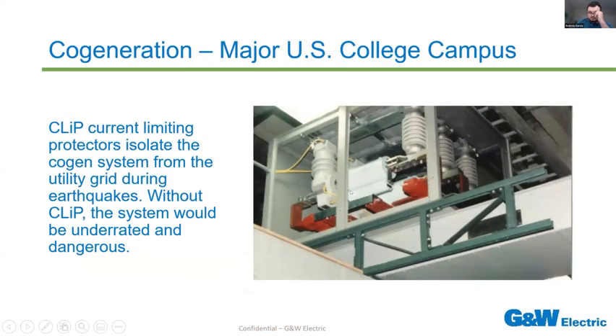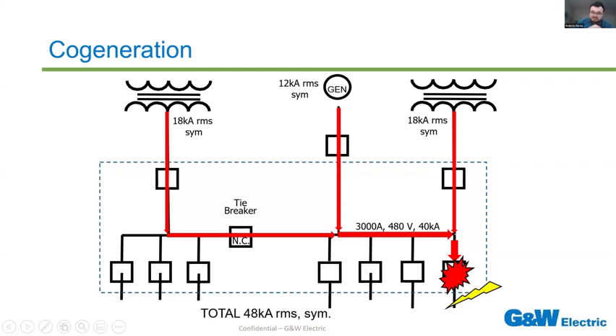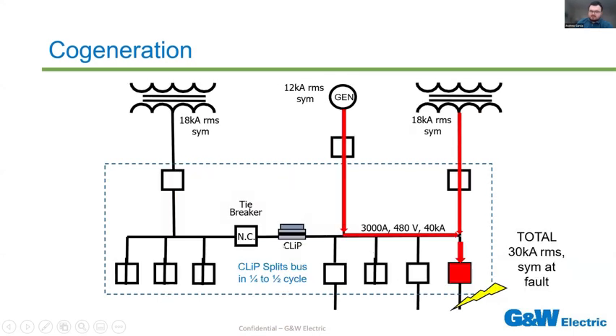Another scenario where I've seen current limiting devices used is at a major US college campus, where current limiting protectors or clips were used to isolate the cogen system from the utility grid during an earthquake. And without the extra protection of the clip, the system could be underrated and dangerous. Here's exactly what that would look like. You have the cogen system tied into the overall grid at a university, where the added fault current from that generator was adding in a lot of fault current that could bring the system past its ratings. They added a clip into that system, specifically at a tiebreaker or at the generator, to intercept that fault current and bring it below the ratings of that device, such that they were able to operate the system appropriately.